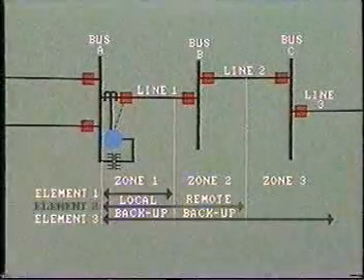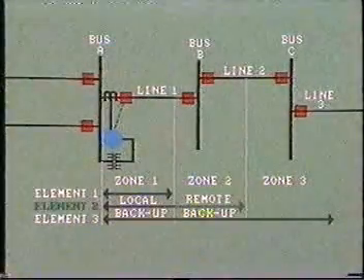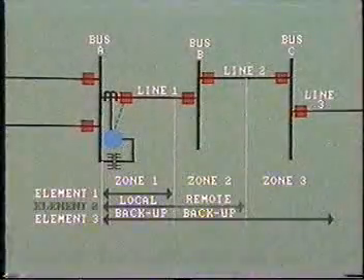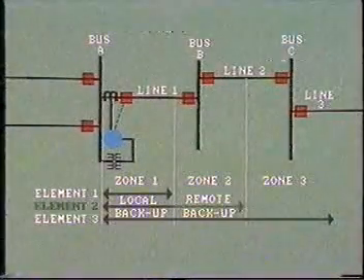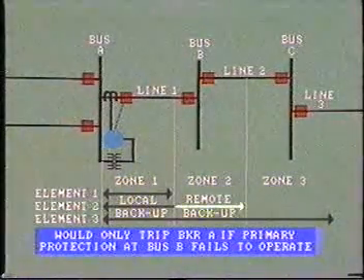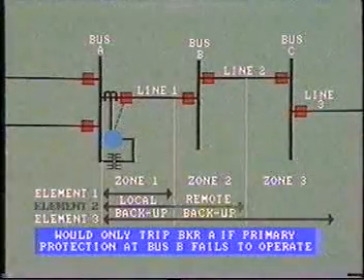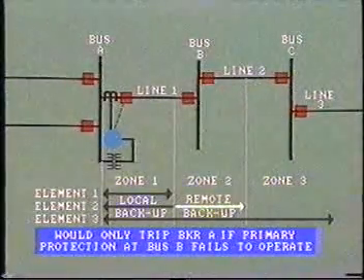The second element also provides remote backup in the case of a fault on bus B or out on line two. This would only operate and trip out breaker A in case the primary protection at bus B failed to operate.